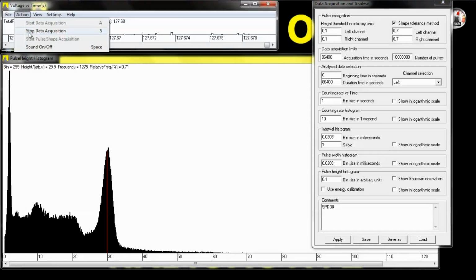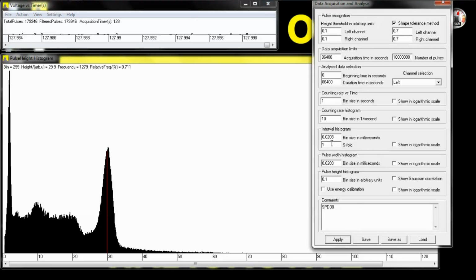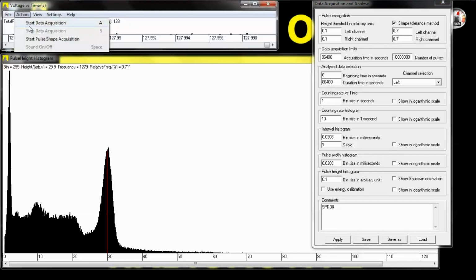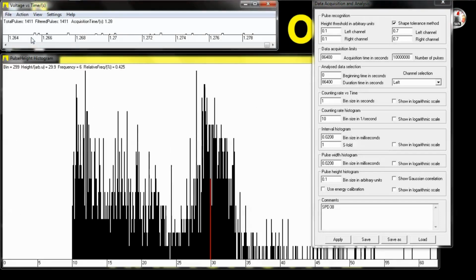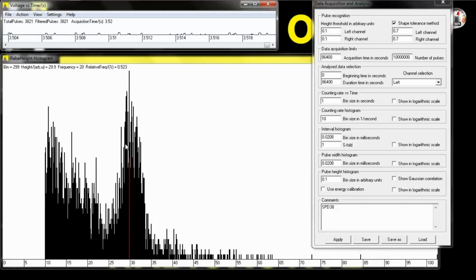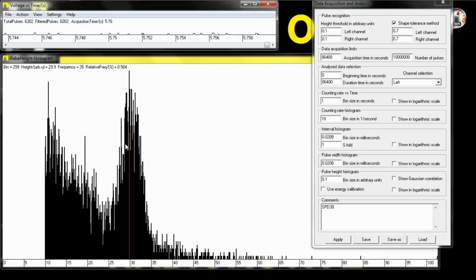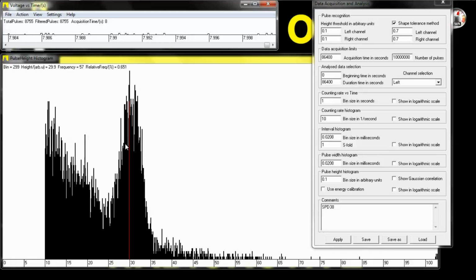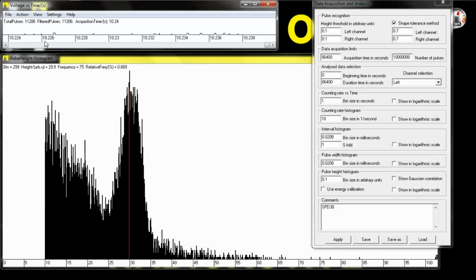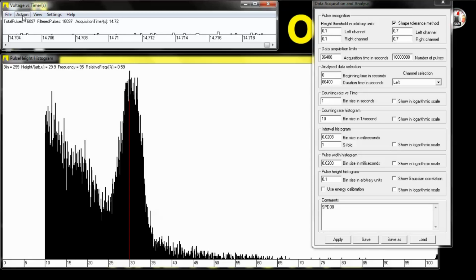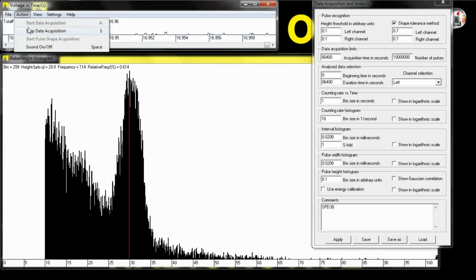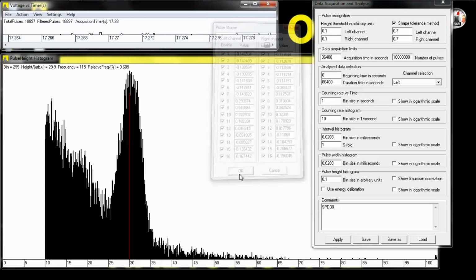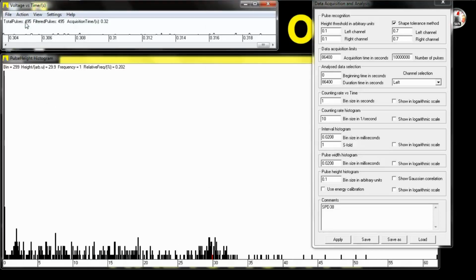All right. We're going to stop the acquisition. We're going to apply this new setting of 0.1. Did I click apply? Yeah, I'll click it a couple times. And we're going to do a start pulse acquisition. And I ignore this pulse height histogram when I'm doing that because it looks all crazy looking. Get a few thousand pulses. Stop it. Accept the new values, and then we're going to run the whole thing.